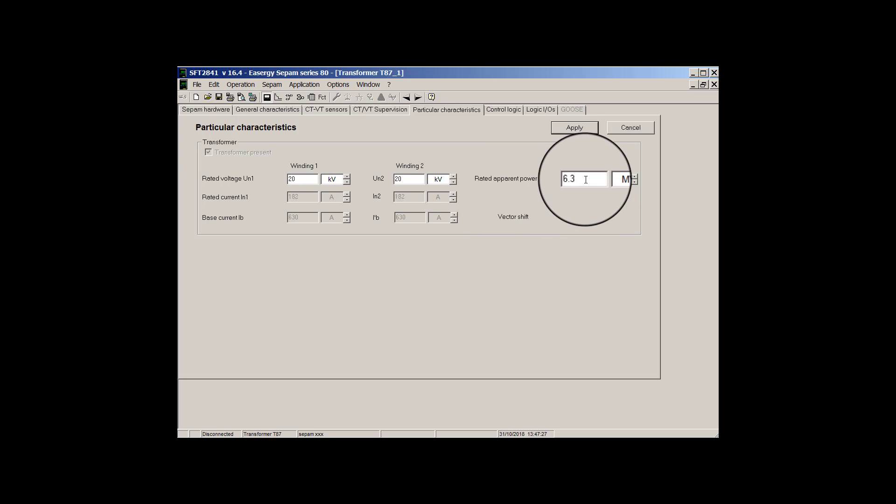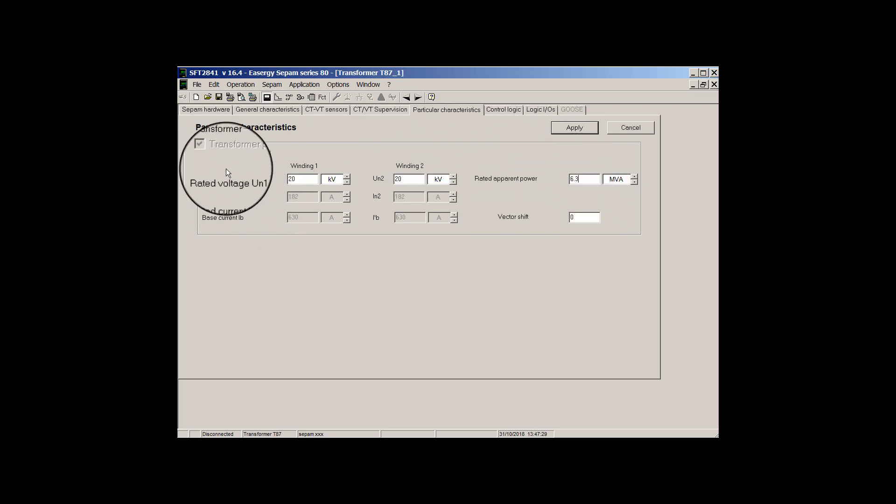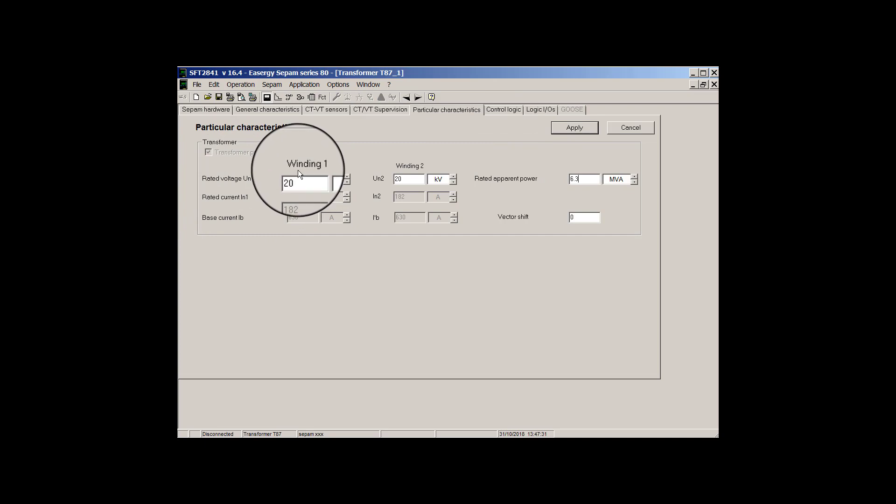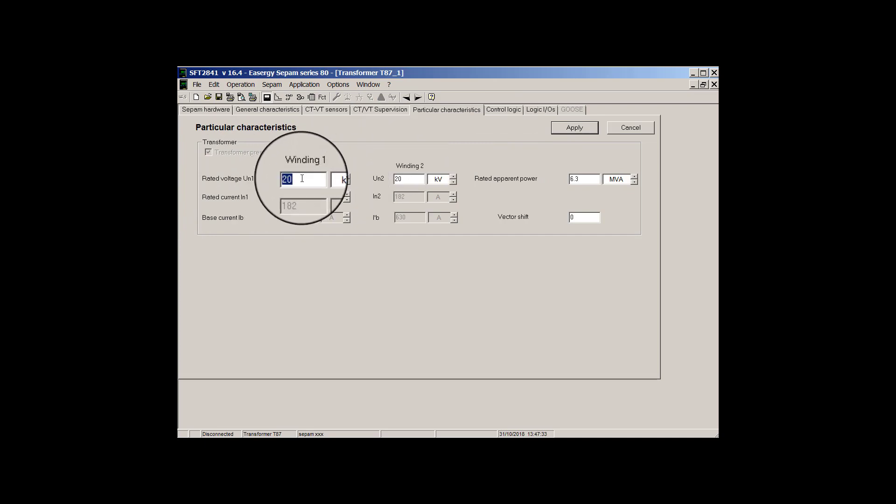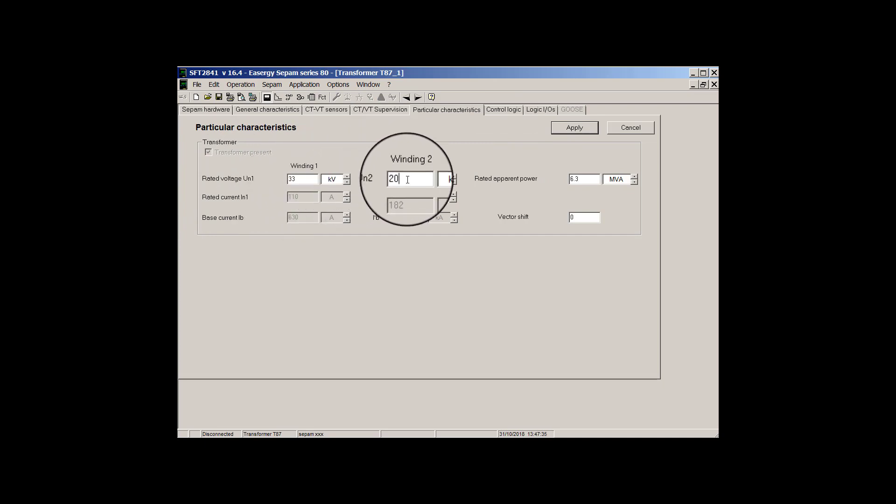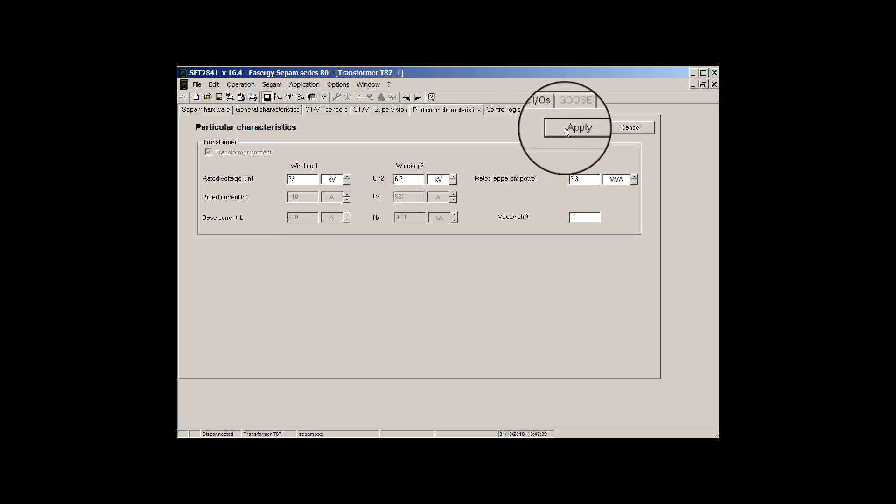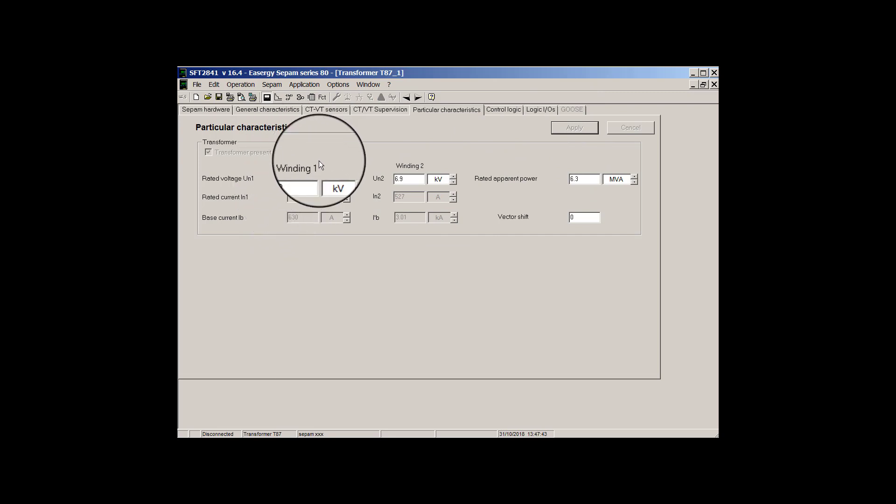So here we can set rated apparent power of transformer. I use my example values so I set it to 6.3 megavolt ampere. Also we can set rated voltage of winding one and winding two here, so I set 33 kilovolt and 6.9 kilovolt. As you see, SFT will calculate the rated current of both windings.